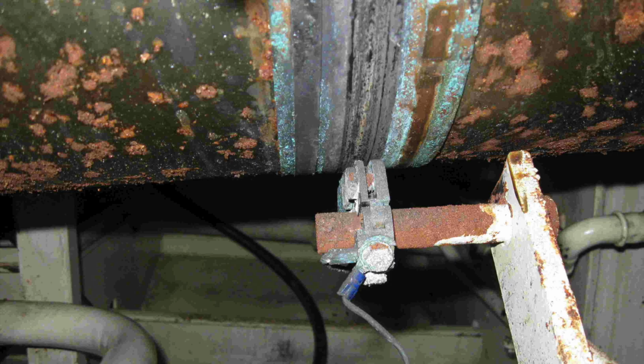Yes, we had an issue on board the frigates, which were using an impressed current cathodic protection system, or I call it an active system, and it wasn't working properly. We went down right to the engine room, and if you think of the shafts, they go out the back through a gland. That doesn't make any direct contact with the ship at the gland hole, the orifice there. So they have to be earthed by another means, and because they're turning, we use a system of slip rings.